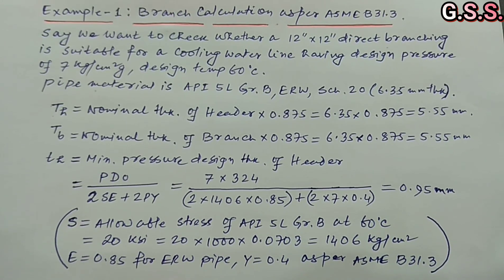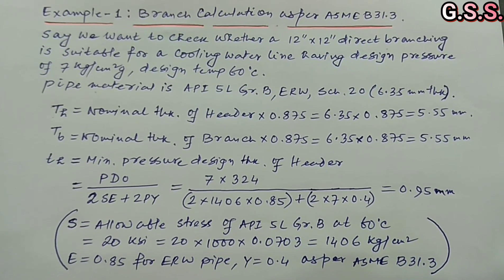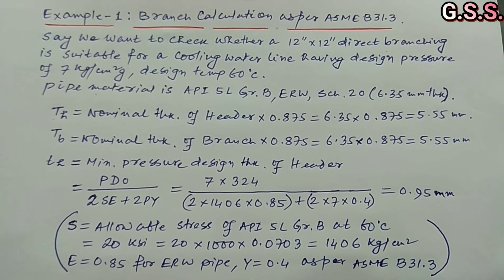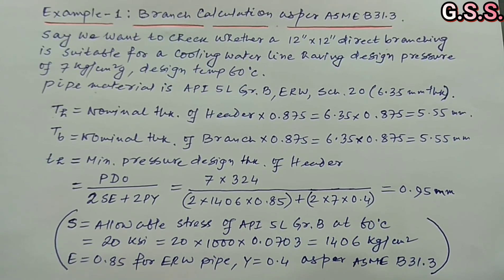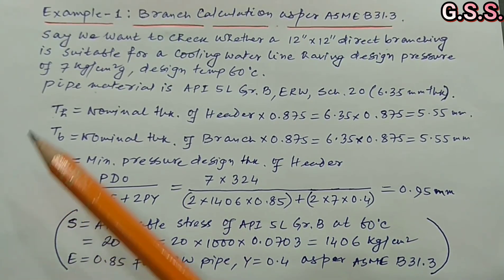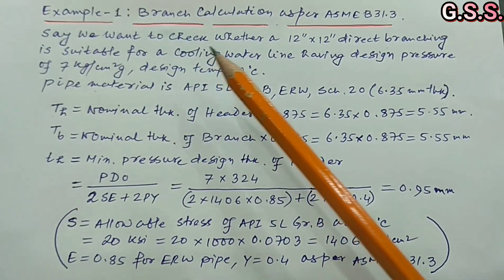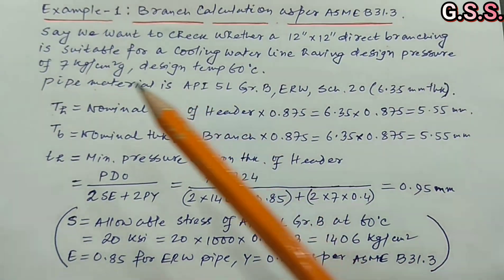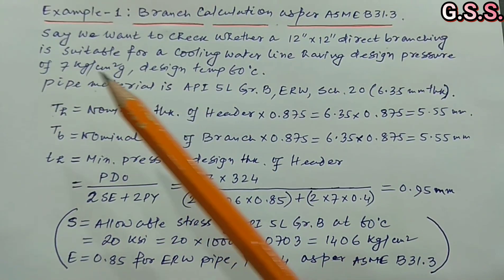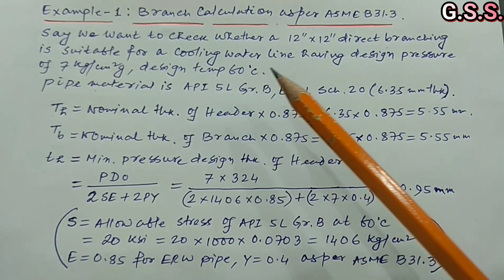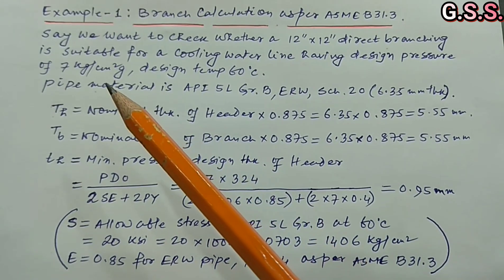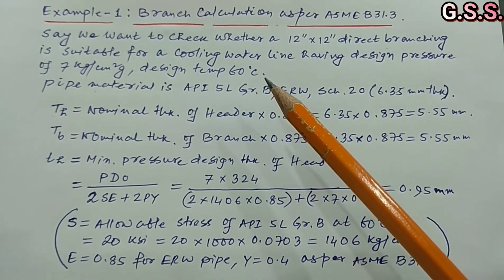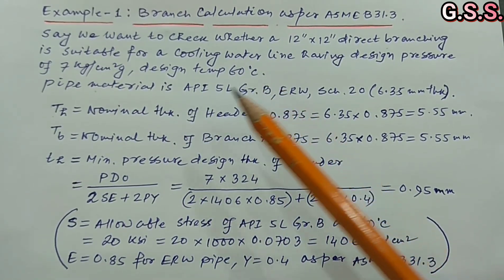Now we will take a few examples of branch calculation as per ASME B31.3. We want to check whether a 12-inch by 12-inch direct branching is suitable for a cooling water line having a design pressure of 7 kg/cm² gauge and a design temperature of 60°C.